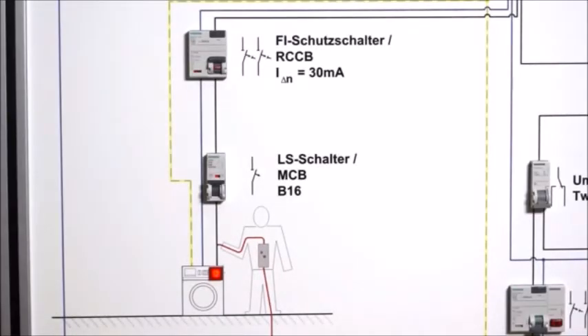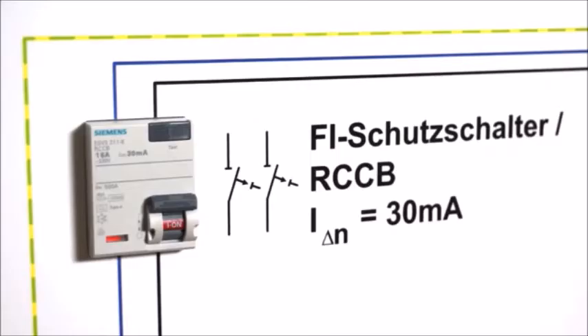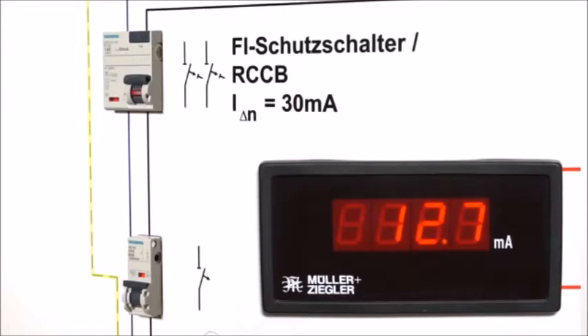You are about to be presented with an everyday situation which shows why RCCBs are so important in the context of personal protection. What you can see is a fault current generated by somebody coming into direct contact with a live component. Such currents pose a risk to personal safety from as little as 30 milliampere. The tripping range of the RCCB is between 15 and 30 milliampere. The simulation shows how the Siemens residual current operated device trips at 22 milliampere and offers effective protection against dangerous shock currents.